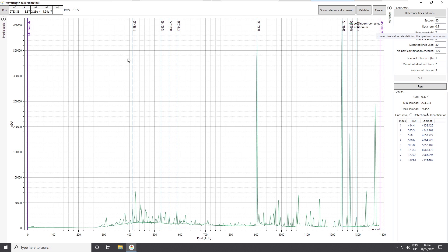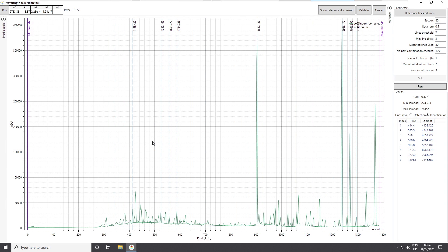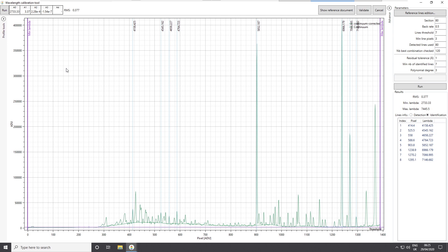We have this list: there is the detection operation that detects all the lines in the spectrum, and then we have the identification step that says, among all these lines, here is the set of lines that I consider to be my reference line set. You can edit this reference line set using the small editor accessible here — you can add and remove lines, or load and store other data.